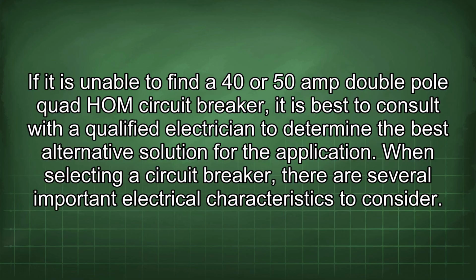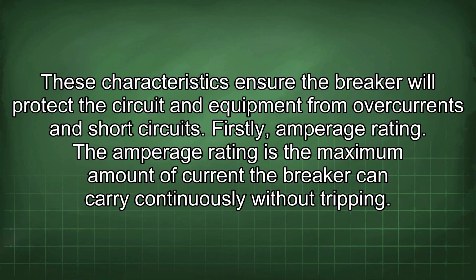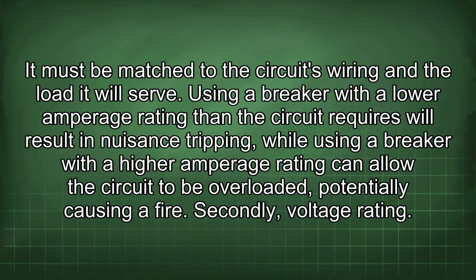When selecting a circuit breaker, there are several important electrical characteristics to consider. These characteristics ensure the breaker will protect the circuit and equipment from overcurrents and short circuits. Firstly, amperage rating. The amperage rating is the maximum amount of current the breaker can carry continuously without tripping. It must be matched to the circuit's wiring and the load it will serve. Using a breaker with a lower amperage rating than the circuit requires will result in nuisance tripping, while using a breaker with a higher amperage rating can allow the circuit to be overloaded, potentially causing a fire.